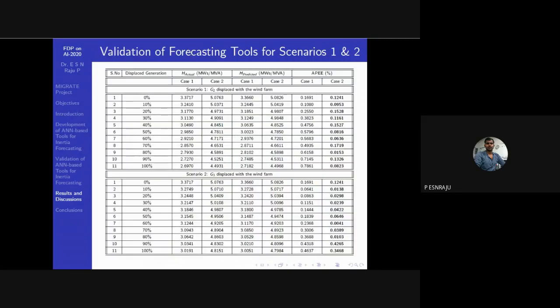This is a comparison for all the cases, showing displaced generation from 0% up to 100%. In scenario one, we have G2 displaced with the wind farm, with two case studies: case 1 excluding induction motor load, case 2 including induction motor load. We observe that case 2 values are larger than case 1, because including the dynamic induction motor load also contributes inertia to the system, giving larger inertia values compared to case 1.